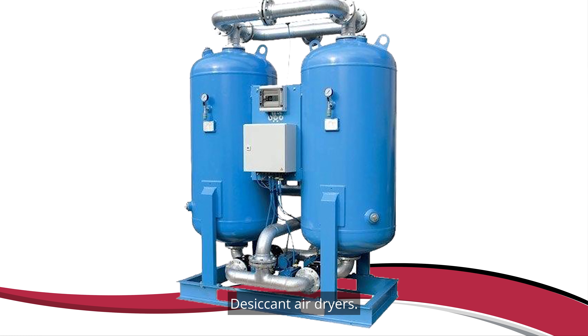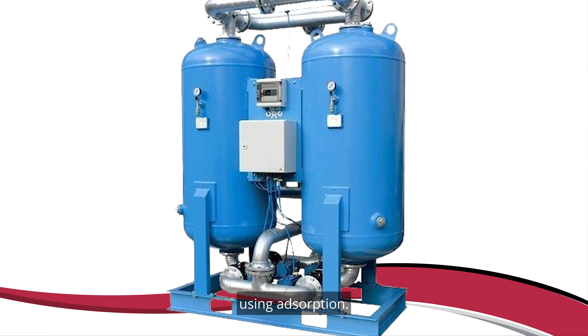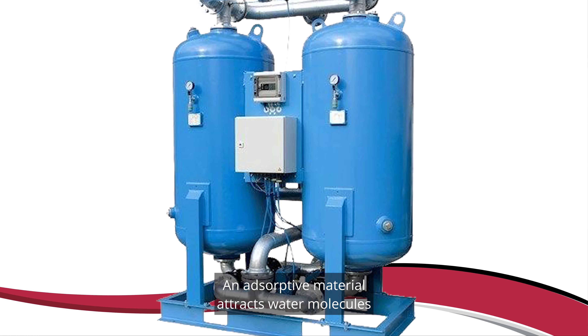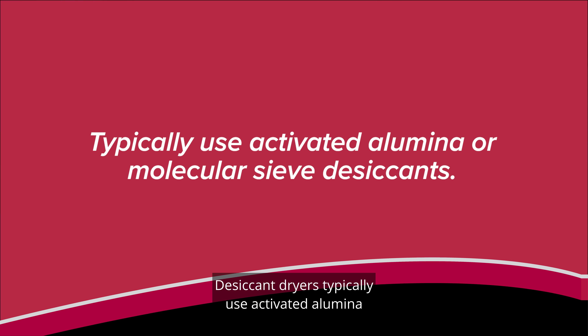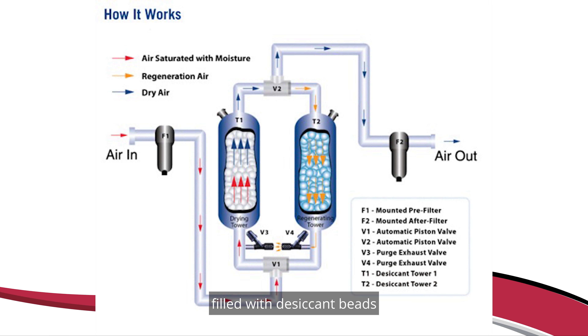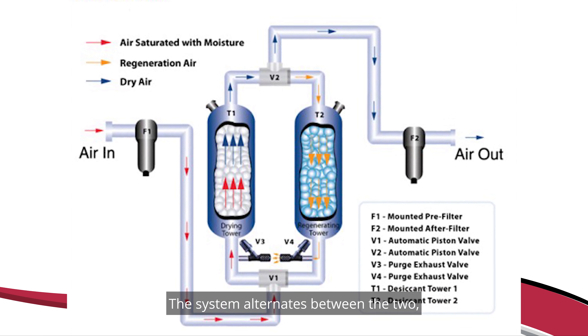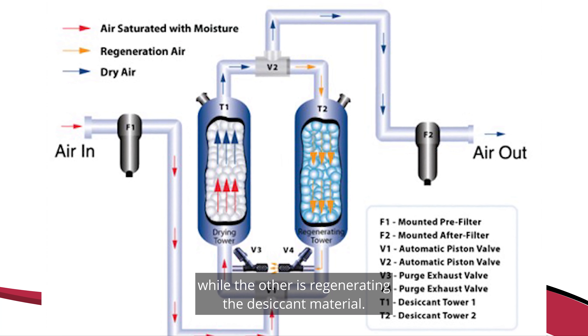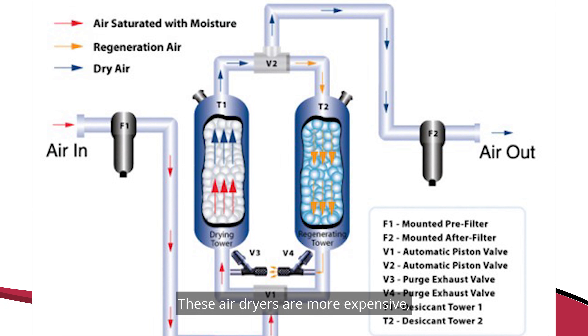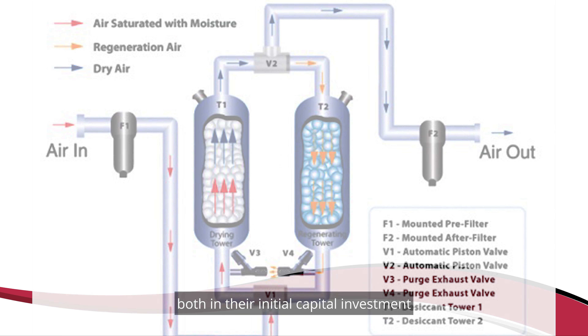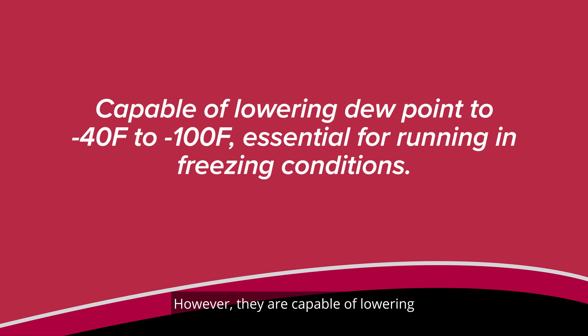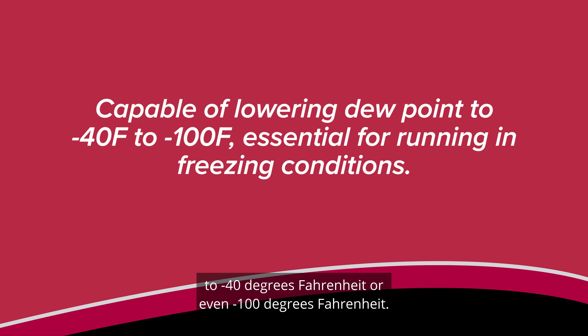Desiccant air dryers work by removing water vapor from the air using adsorption. An adsorptive material attracts water molecules and binds them to the surface of the material. Desiccant dryers typically use activated alumina or molecular sieve desiccants. Most desiccant air dryers have two towers filled with desiccant beads to allow for continual operation. The system alternates between the two, allowing one to dry the compressed air while the other is regenerating the desiccant material. These air dryers are more expensive in both initial capital investment and operating and maintenance costs. However, they are capable of lowering the dew point to minus 40 degrees Fahrenheit or even minus 100 degrees Fahrenheit.